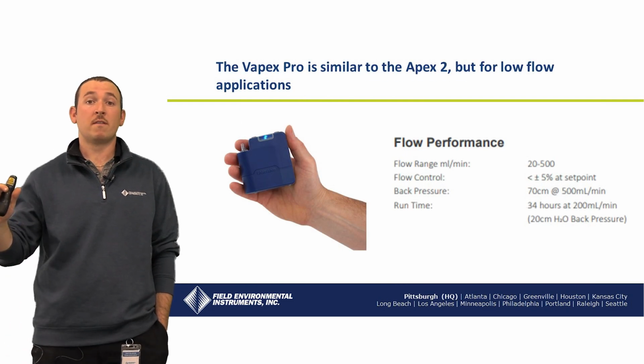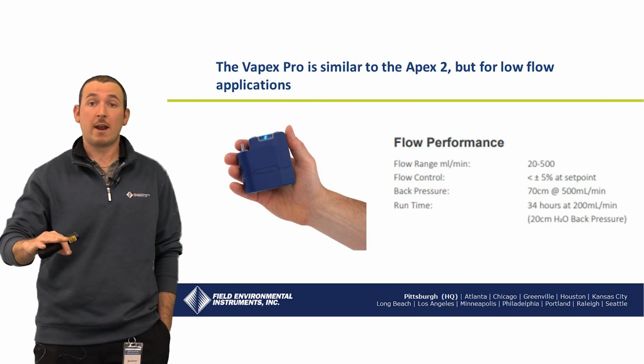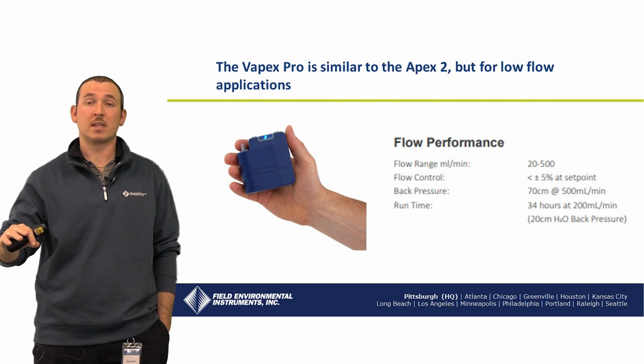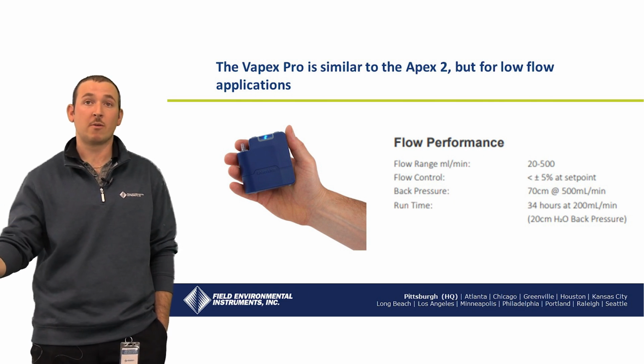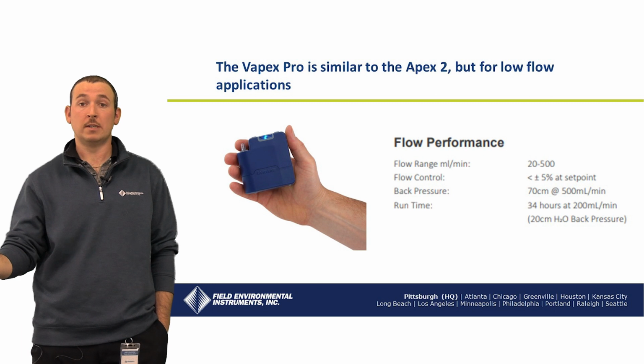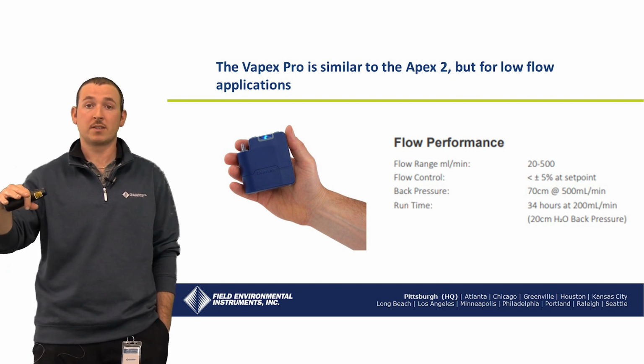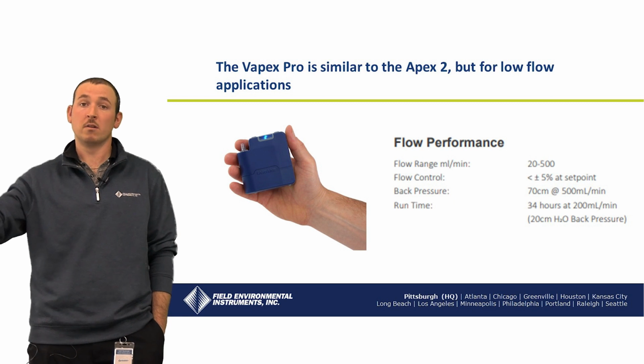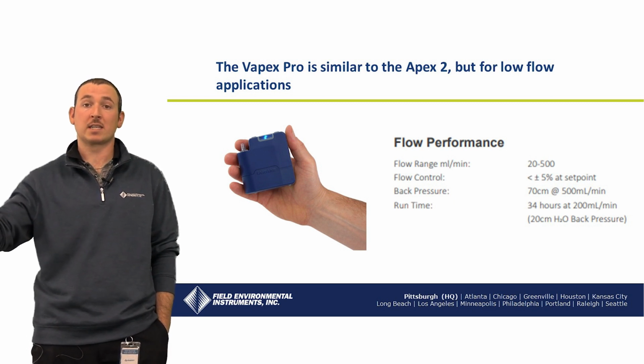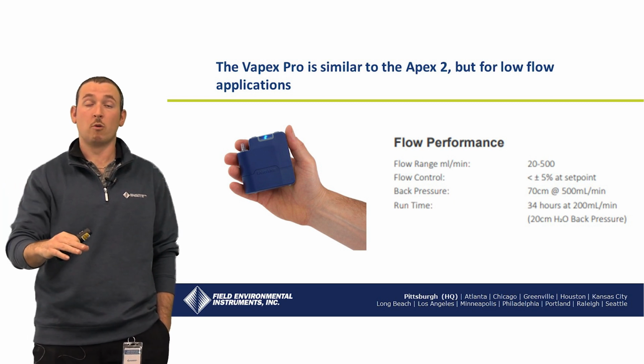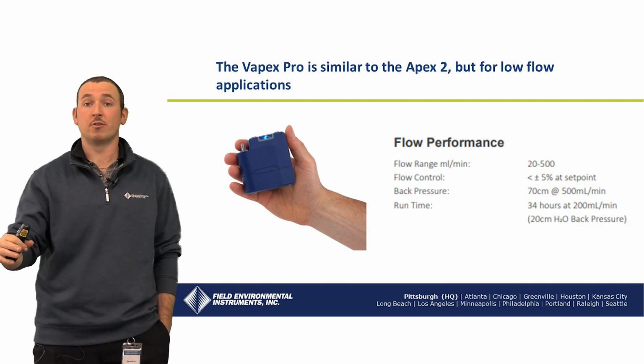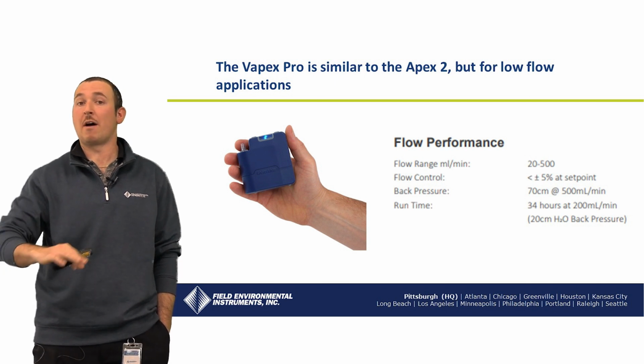So if you need to run some low flow air sampling, rather than using the Apex 2, one other option that you have is to use the Vapex Pro. Where the Apex 2 hits that middle ground of flow rates, that 1,000 to 5,000 milliliters per minute, the Vapex Pro runs lower than that. It will run at 20 to 500 milliliters per minute without any adapters necessary.